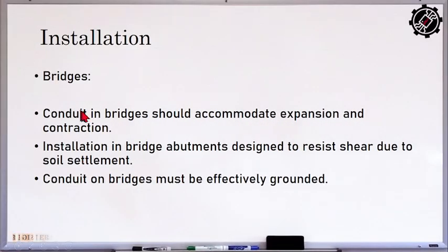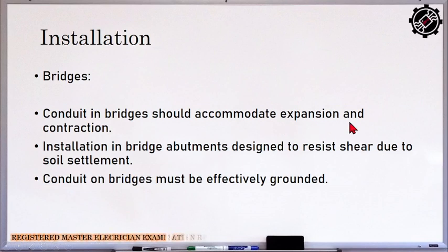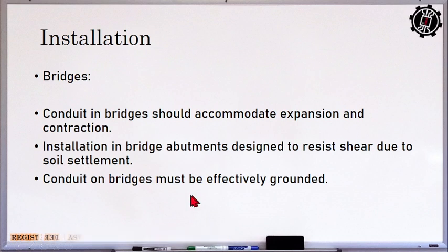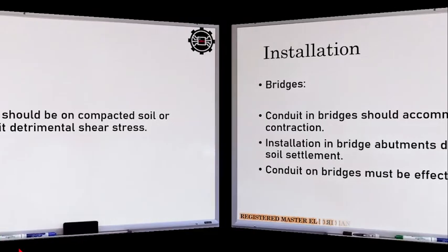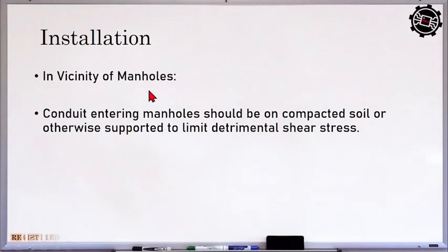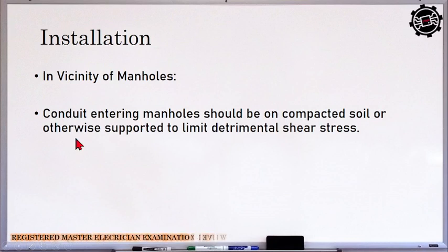Okay. If bridges, no, conduit in bridges should accommodate expansion and contraction. No? Kasi yung bridge naman meron siyang expansion and contraction. So dapat yung ating conduit is ganun din. No? Installation on bridge, abutments designed to resist shear due to soil resettlement. No? Tapos conduit on bridges must also be effectively grounded. Then vicinity of manholes. So conduit entering manhole should be on compacted soil or otherwise supported to limit detrimental shear. So yan yun if our conduit is near the vicinity of manholes.